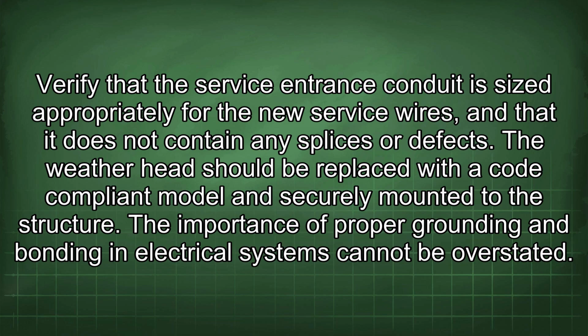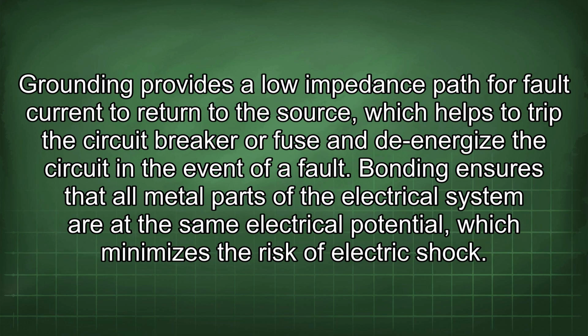The importance of proper grounding and bonding in electrical systems cannot be overstated. Grounding provides a low impedance path for fault current to return to the source, which helps to trip the circuit breaker or fuse in the event of a fault. Bonding ensures that all metal parts of the electrical system are at the same electrical potential, which minimizes the risk of electric shock.